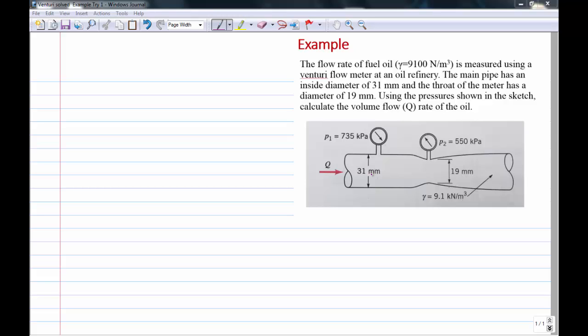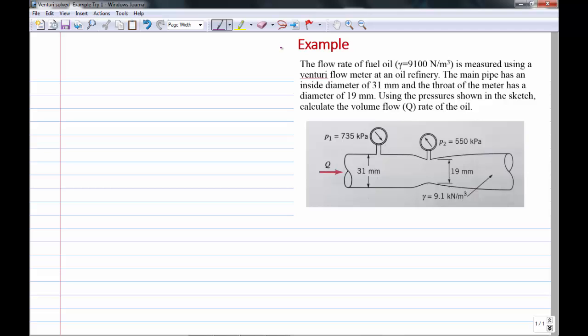This is a numerical example of using a Venturi flow meter to solve for fluid flow in a pipe. The problem states: the flow rate of fuel oil, which has a specific weight of 9100 newtons per cubic meter, is measured using a Venturi flow meter at an oil refinery. The main pipe has an inside diameter of 31 millimeters, and at the throat the diameter is 19 millimeters. Using the pressures shown on the sketch, calculate the volume flow rate of oil.